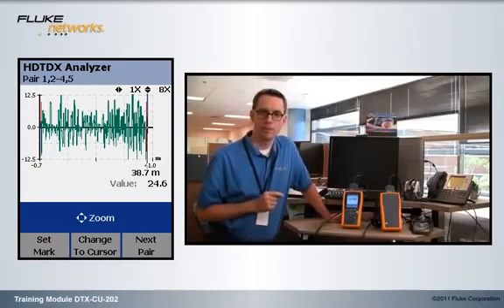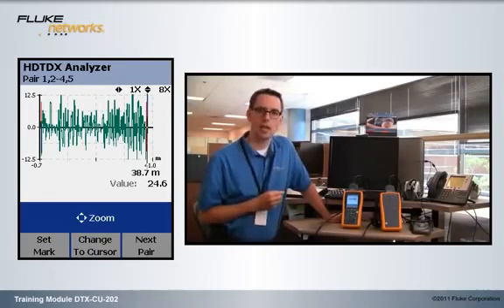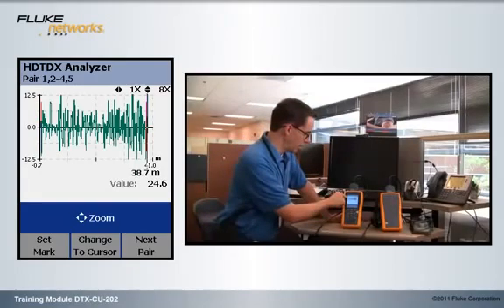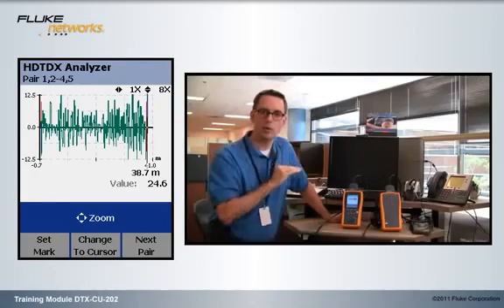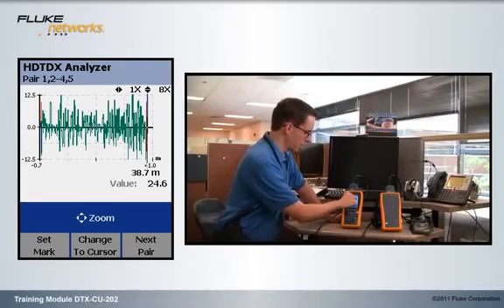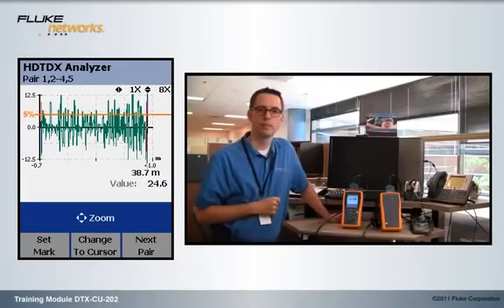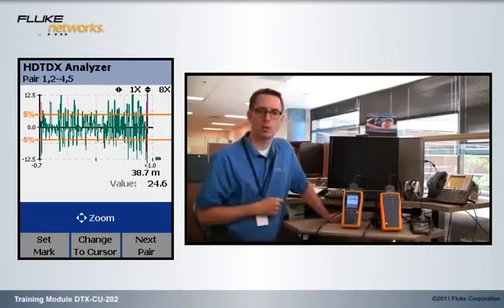A general rule of thumb, and it's not in the standards, this is just a diagnostic tool, is that we don't want to see more than 5% happening in the cable. So 5% just happens to be a little bit less than halfway on the screen here. Let's put in those two markers, the 5% marker across the top and the 5% marker along the bottom.